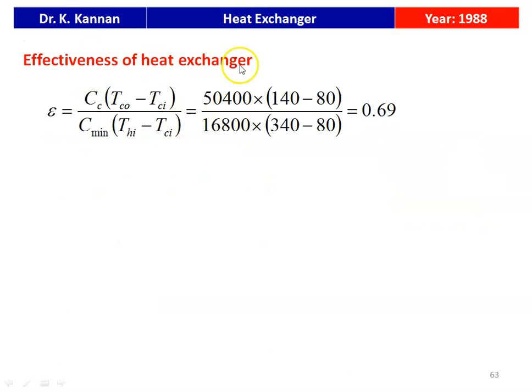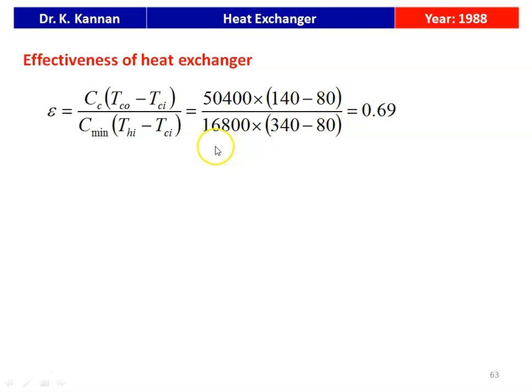The effectiveness of the heat exchanger: ε = CC × (TCO − TCI) / (C_min × (THI − TCI)) = 50,400 × (140 − 80) / (16,800 × (340 − 80)) = 0.69. So the effectiveness of the heat exchanger is 0.69.